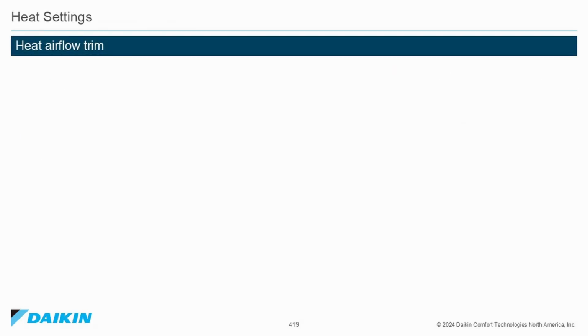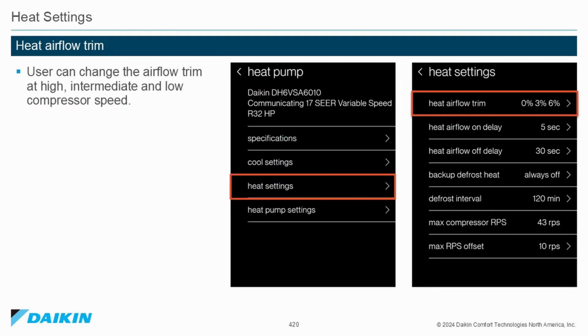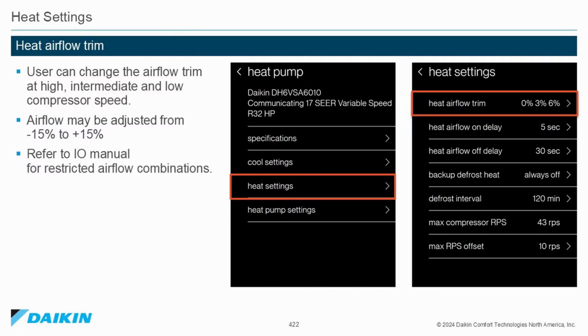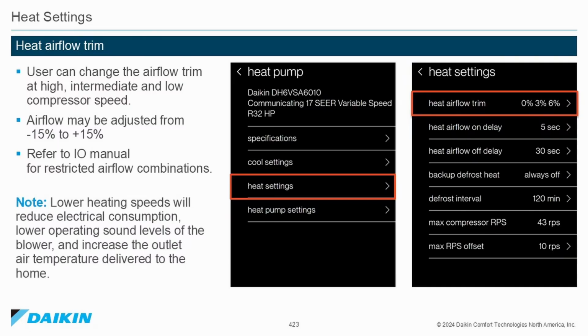Heat settings. Heat airflow trim. The user can change the airflow trim at high, intermediate, and low compressor speed. Airflow may be adjusted from -15% to +15%. Refer to the I/O manual for restricted airflow combinations. Note: lower heating speeds will reduce electrical consumption, lower operating sound levels of the blower, and increase the outlet air temperature delivered to the home.